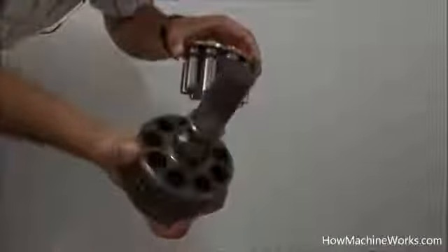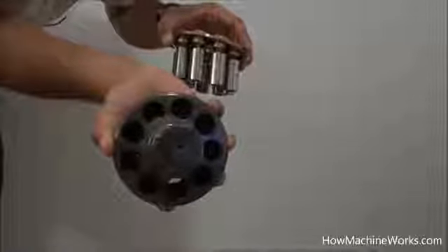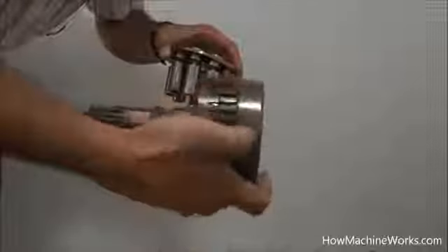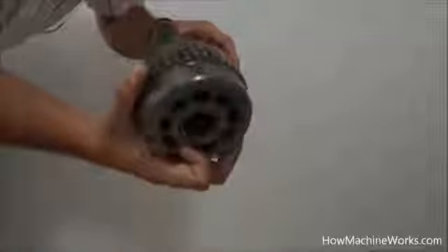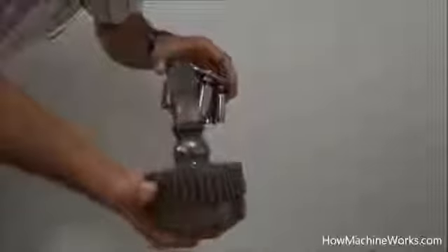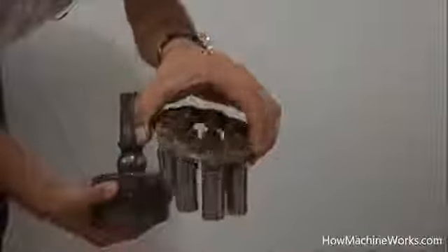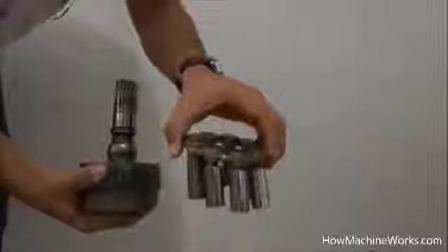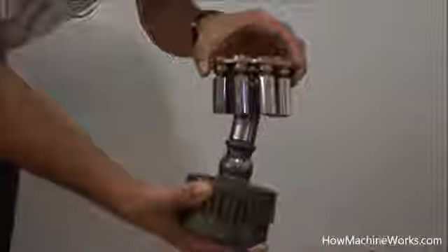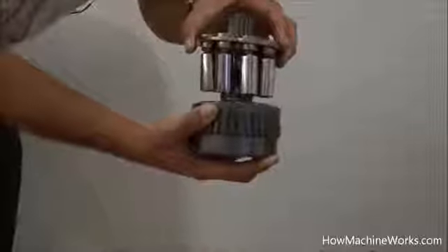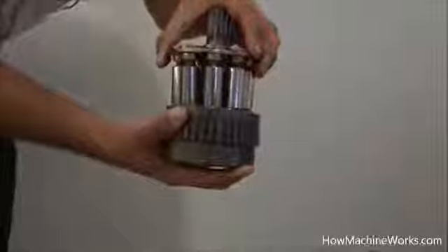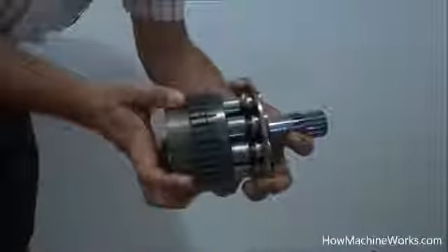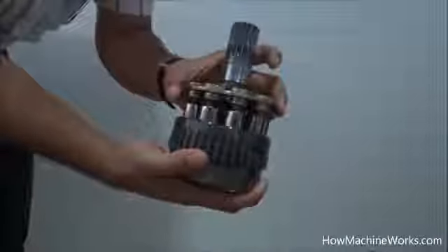Now you can see the pistons which I have shown, and these are the holes where the pistons will actually be inserted, right? Okay, now you can see the cylinder once again at a different angle. Now we'll be putting the pistons back into the cylinder block, and let's see how it can be assembled back. Make sure that once a piston is removed, it should be given back into the same pot and should not be changed, because they have already mated, and scoring marks will be like a male-female scoring mark, so it has to be inserted in the same pot. So that's how it looks.